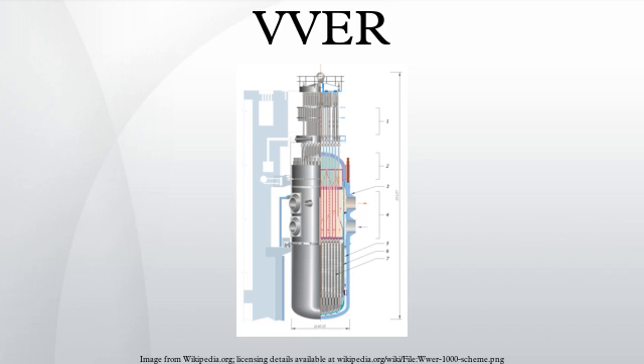A typical design feature of nuclear reactors is layered safety barriers preventing escape of radioactive material. VVER reactors have four layers: fuel pellets, in which radioactive elements are retained within the crystal structure; fuel rods, where zircaloy tubes provide a further barrier resistant to heat and high pressure; a reactor shell, a massive steel shell that encases the whole fuel assembly hermetically; and a reactor building, a concrete containment building encasing the whole first circuit, strong enough to resist the pressure surge a breach in the first circuit would cause. Currently operating Russian VVERs are inherently safer designs than the RBMK reactors of the Chernobyl disaster.